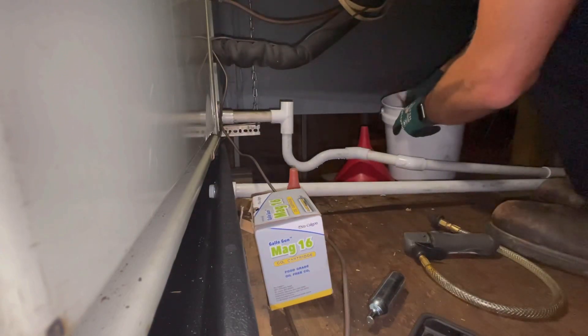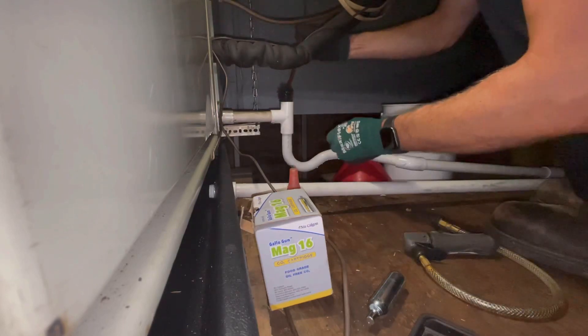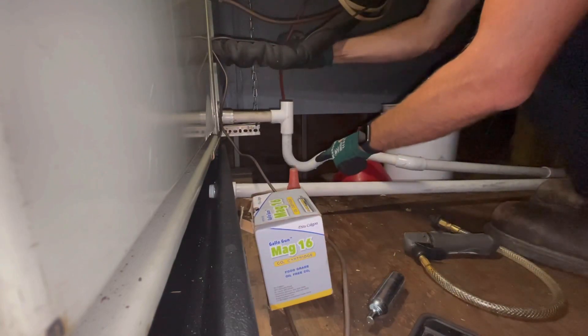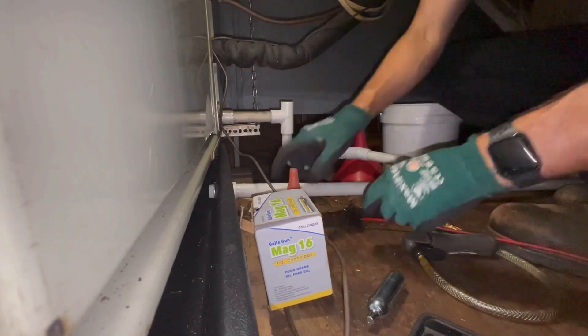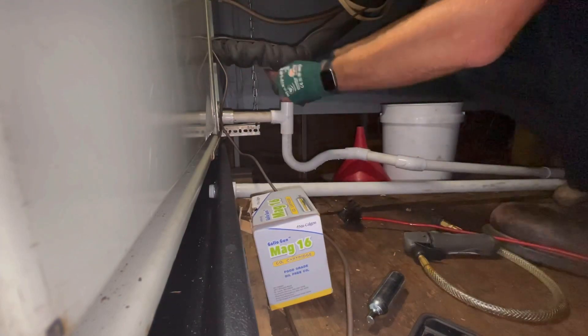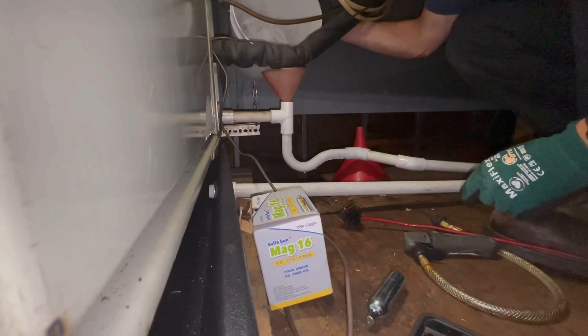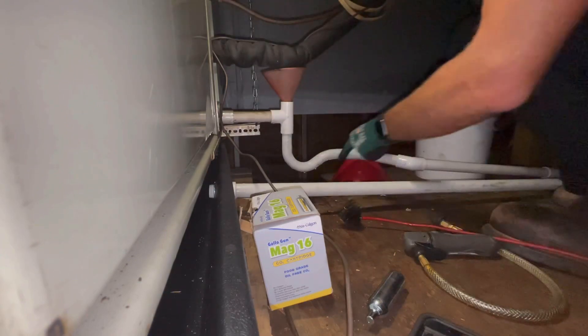I like to rinse it off with a little bit of water, then straighten that tip out and go straight down in there. So right now I'm probably about here in this trap, brushing that out with this tip. After that, I'll typically take a funnel — I'll set it right on top — then I'll take usually hot water or a mixture of hot water and EVAP coil cleaner and flush down that trap, making sure it flushes out.